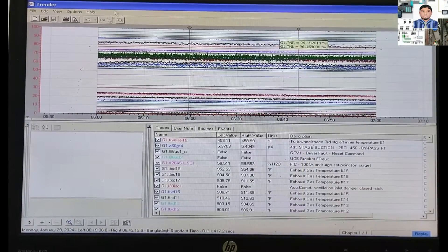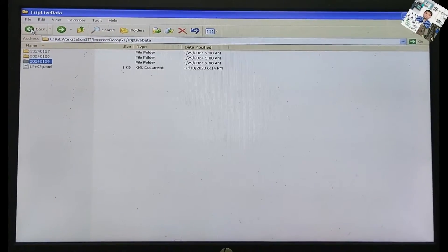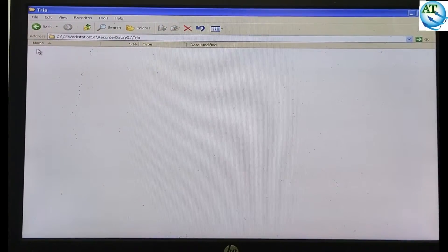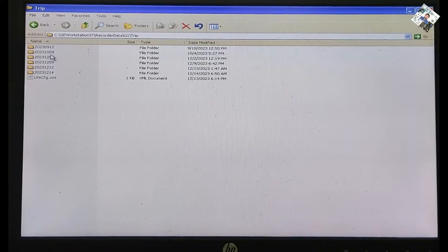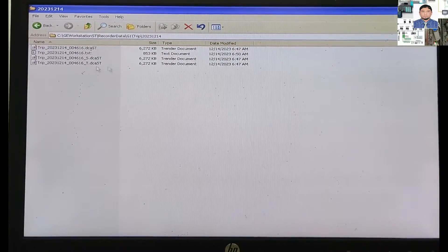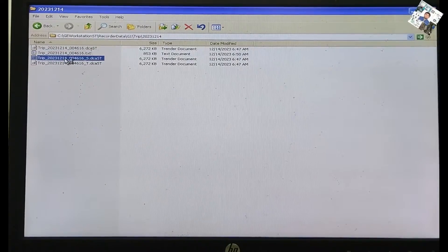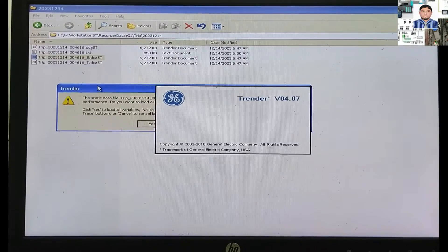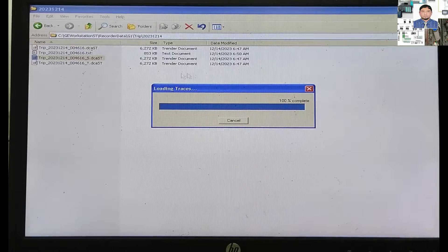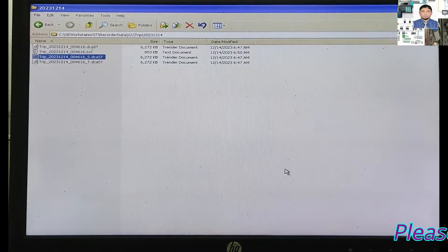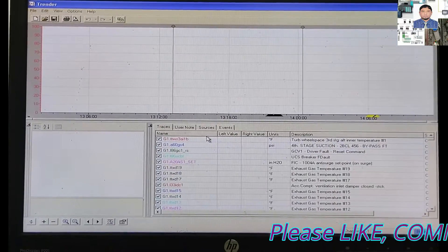Here different options are available. Traces mean the tags you have already covered. Now I will see the TRIP data — this is the TRIP Live Data. Now I will show the TRIP data. Here the TRIPs are in different data folders and all the data are stored. You can see one date — December 2023 — one of the TRIPs. Press double-click and press the yes button. Then the TRIP data will load and you can see the different trends of this TRIP. By analyzing this, you can understand for which reason the turbine TRIPped.